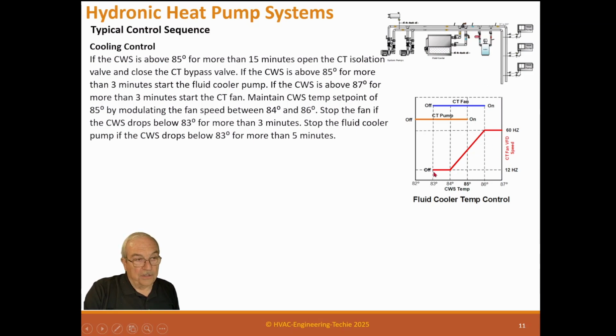When it's on, it will ramp from minimum 12 hertz, clear up to maximum 60 hertz, depending on the water temperature from 84 to 86. And it does that to maintain 85 degrees. So it will modulate up and down until the temperature gets below 83 degrees, and then it will shut the fan off.